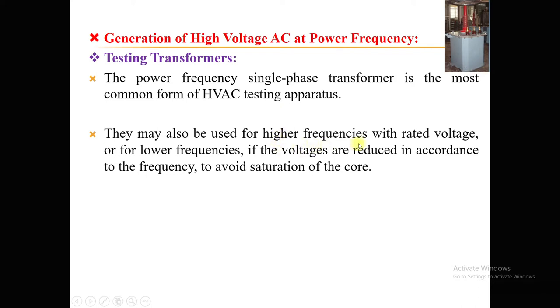We use lower frequencies with reduced voltage levels to avoid saturation of the core. Depending on the frequency requirement, the material used for the core of the testing transformer also differs, because we need to manage core saturation. If the core saturates due to frequency variation, it may inject harmonics, which would hinder evaluation of the high voltage equipment's performance under AC.